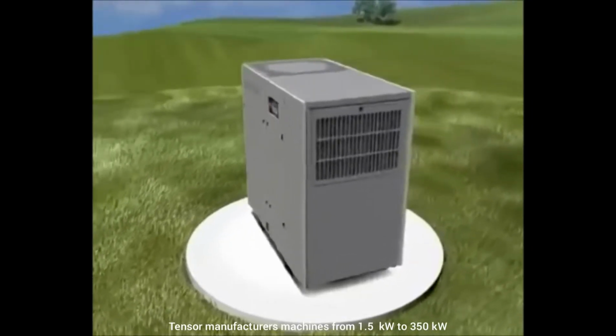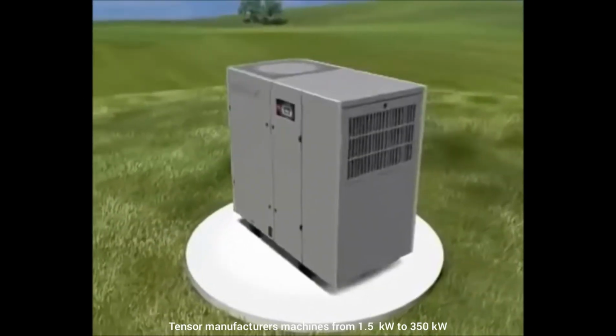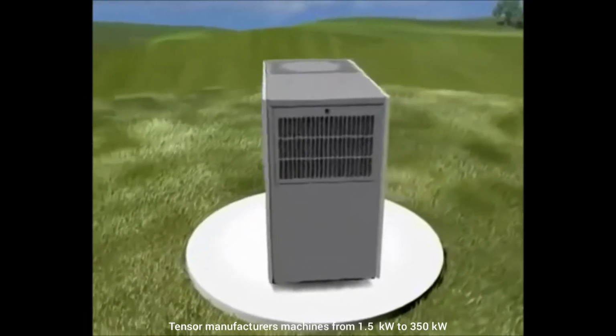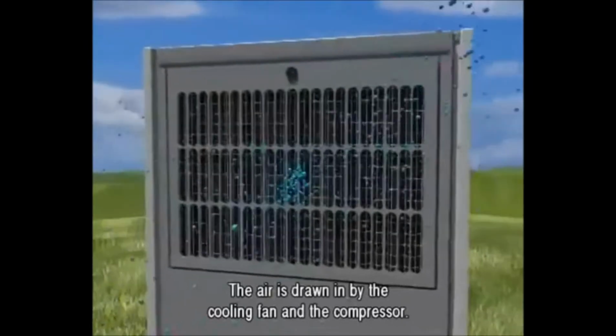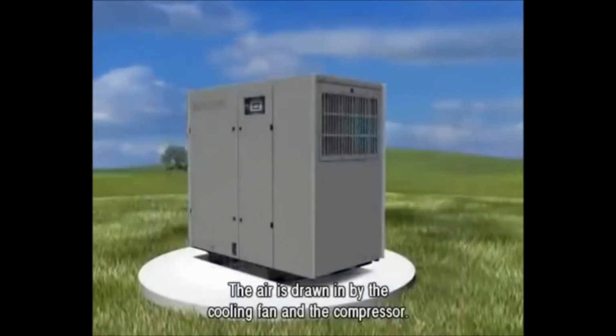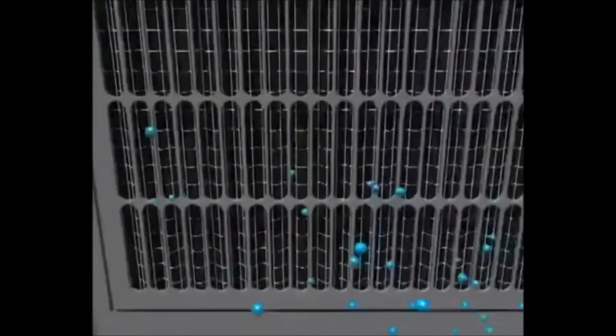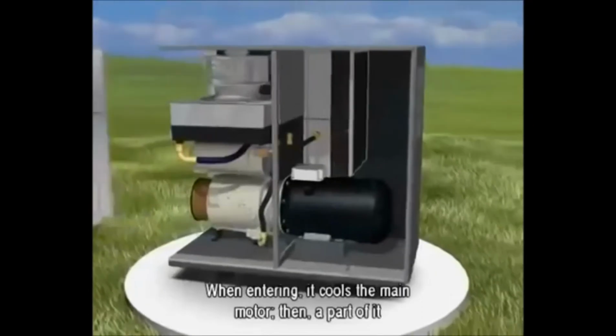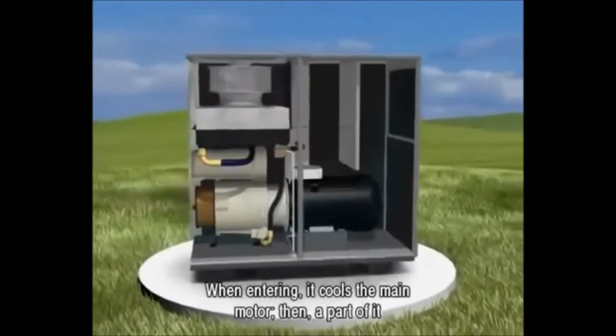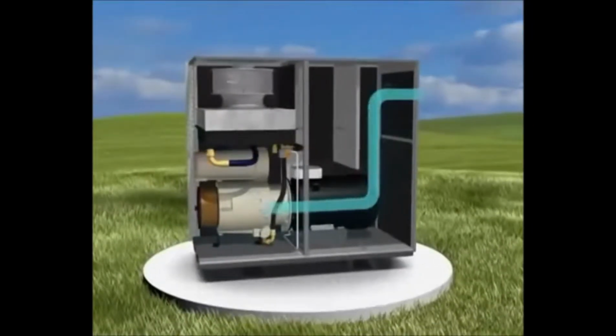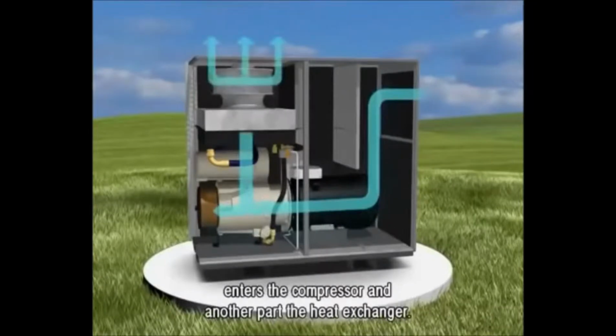Tensor manufactures machines from 1.5 kilowatt to 350 kilowatt. The air is drawn in by the cooling fan and the compressor. When entering, it cools the main motor, then a part of it enters the compressor and another part the heat exchanger.